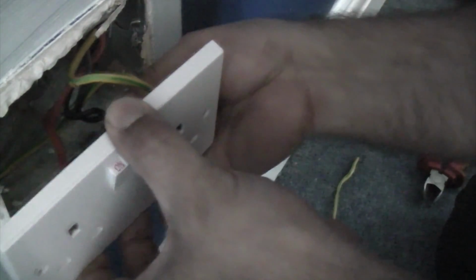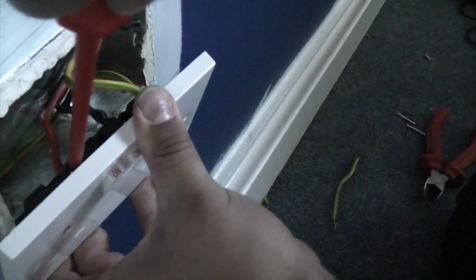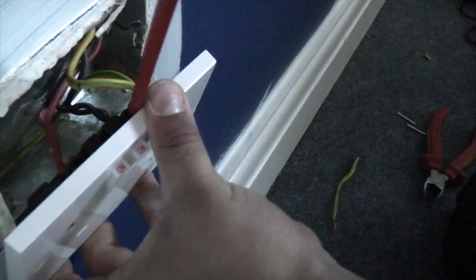It's important when you've done something like this that you check that all your connections are tight. So you need to get hold of each wire and see if you can physically pull it out with your fingers. And if you can pull the wires out, you've not tightened them correctly in the first place. So you need to loosen it off, put them back in and tighten it up again. Now before we put this back on, we're just going to check that they are all tight. So that's the socket fitted now.